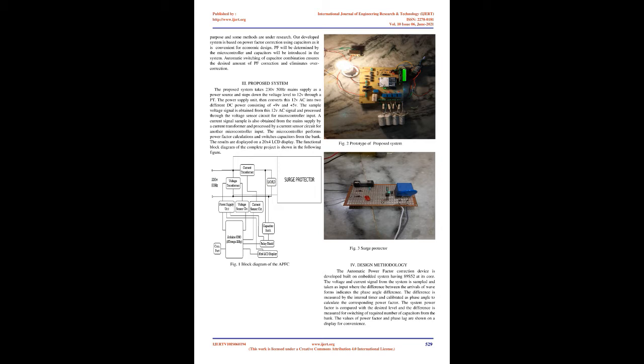Static capacitor bank. The application of shunt capacitor banks results in a decrease in the magnitude of the source current, improves the power factor and consequently improves voltage regulation throughout the system. However, shunt capacitor banks do not affect current or power factor beyond their point of application. Capacitor banks can be fixed, switched, or a combination of both. The switching process can be manual or automatic. Capacitor banks are rugged and simple to configure and install. Other methods: there are also some other complicated methods invented for PF correction which are not very popular for economic reasons. IJERT 10 IS 060194.